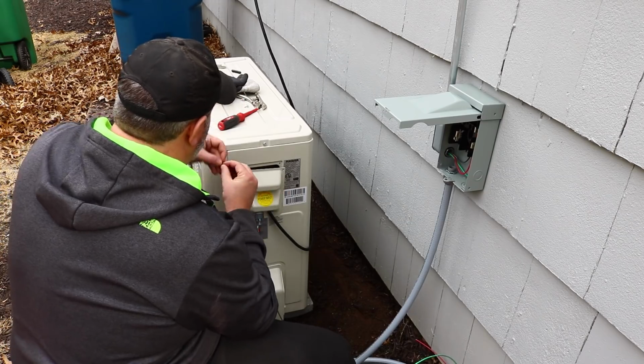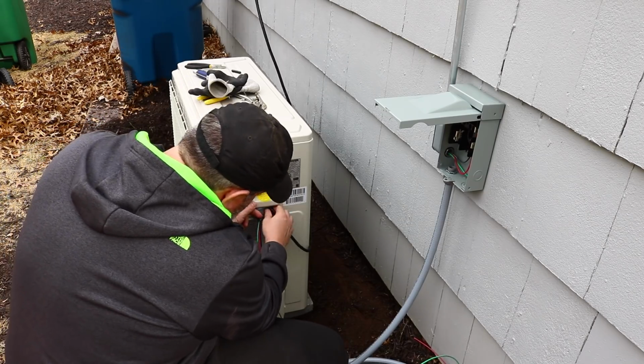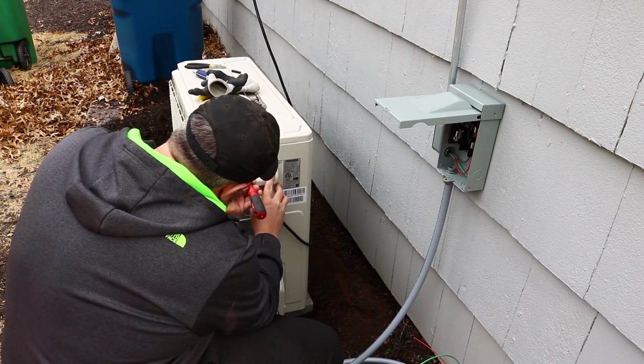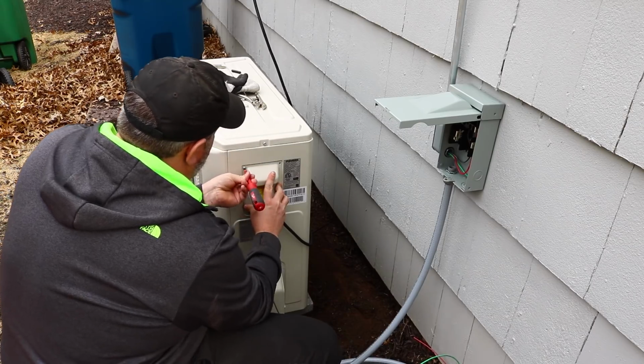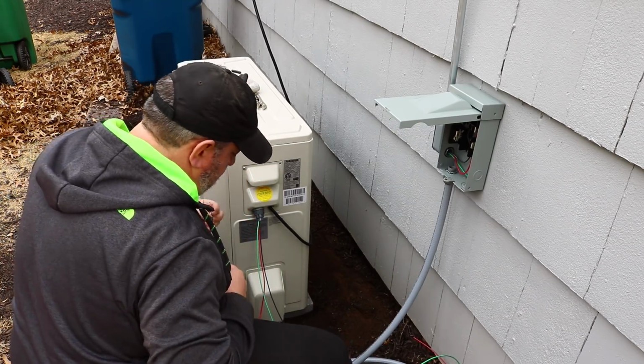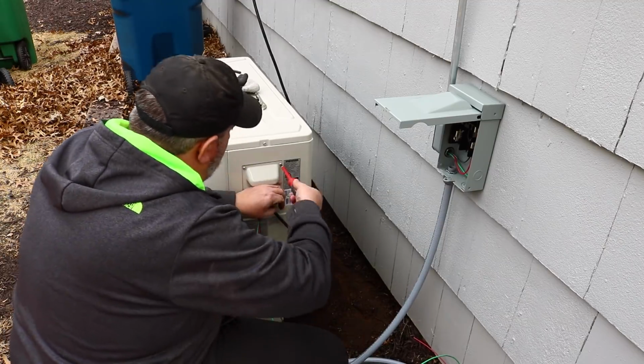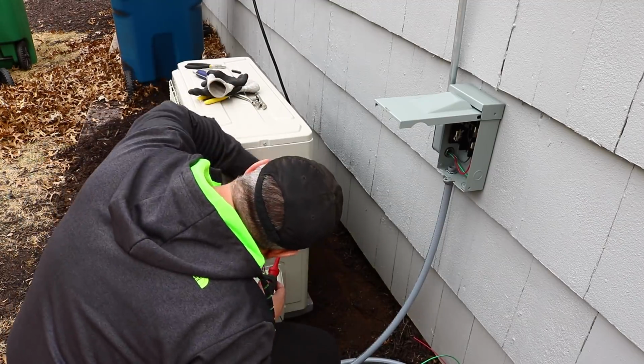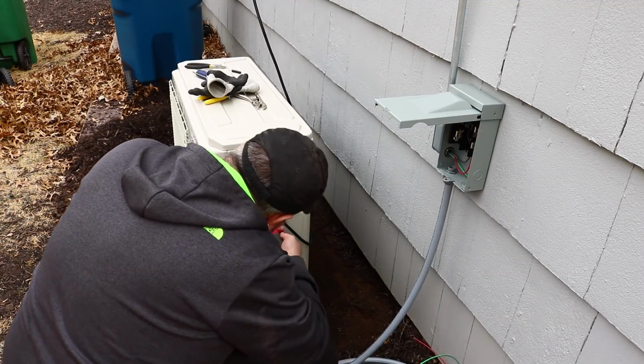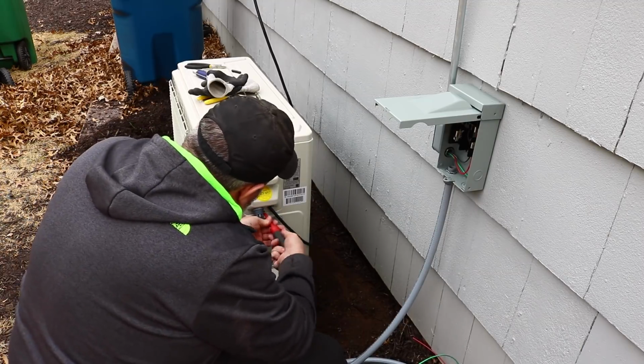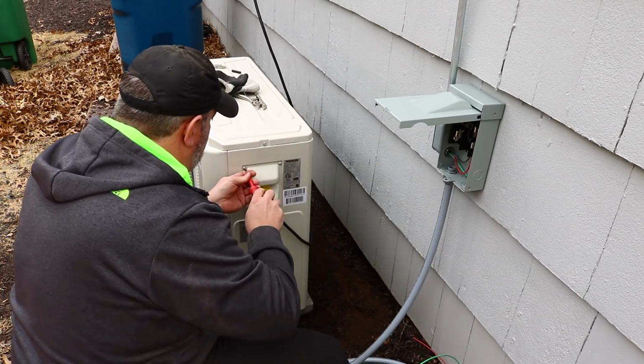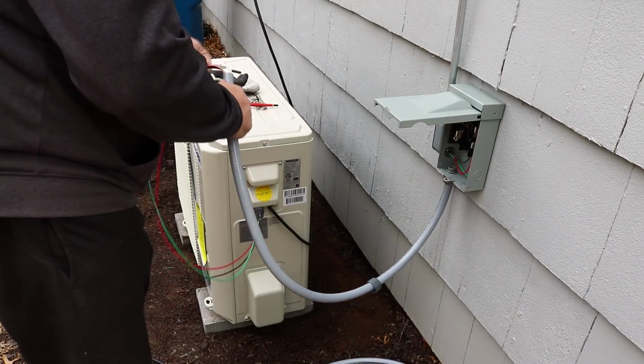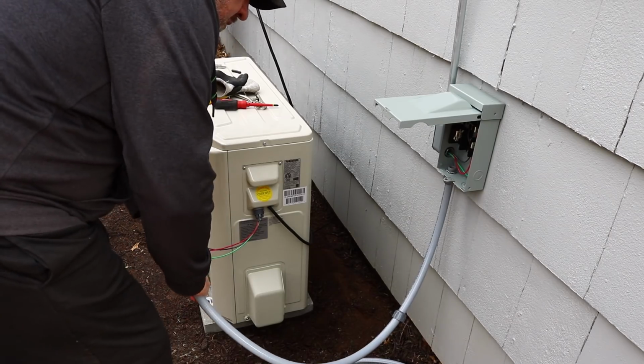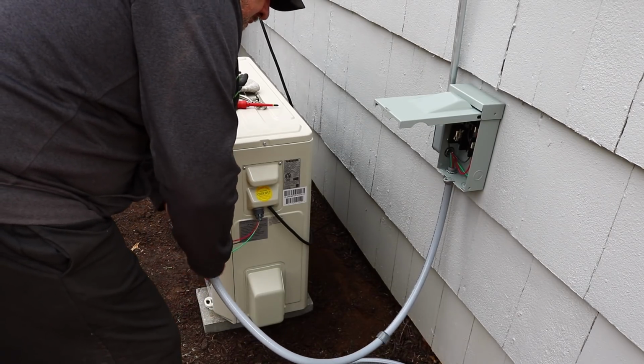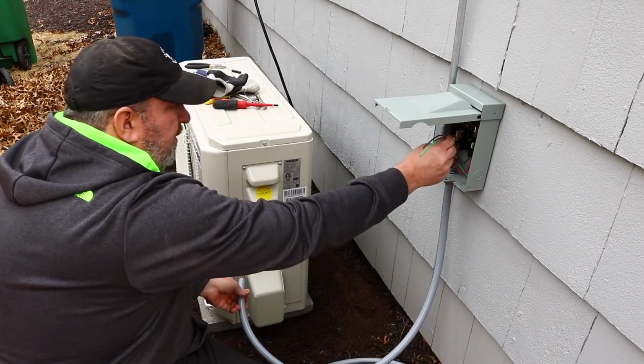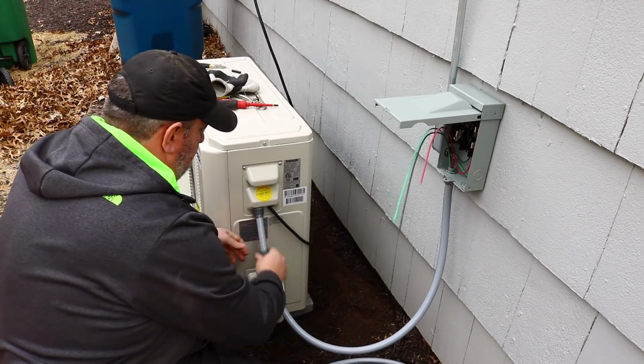A couple things to note here. One, make sure when you are connecting the signal wire that you've run it through the terminal cover first, or else you'll have to take it off and run it back through and reconnect it. Second, I had shown earlier that I connected the liquid tight to the terminal cover, and what I actually did is I ended up taking it off and doing all the connections on the outdoor unit and then feeding it through the terminal cover, through the liquid tight, connecting the liquid tight, and then running it all the way up into the disconnect box.